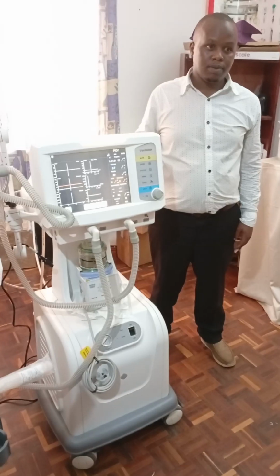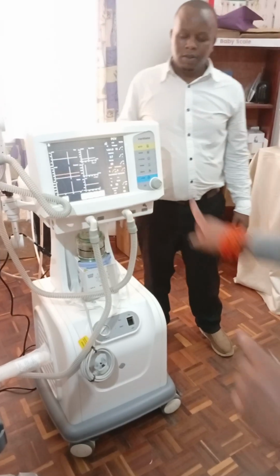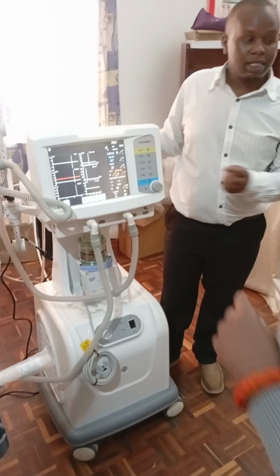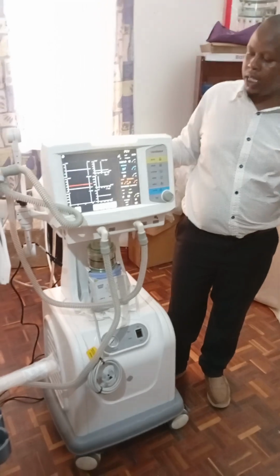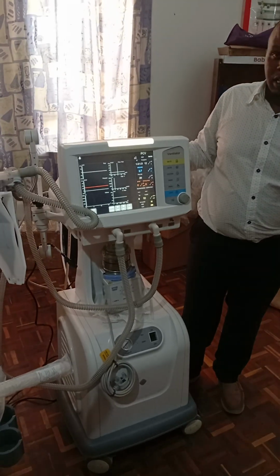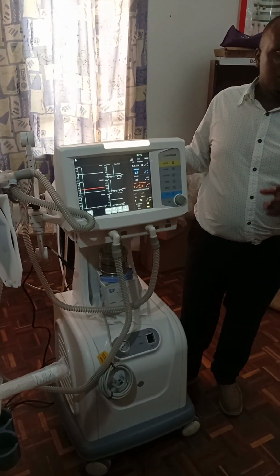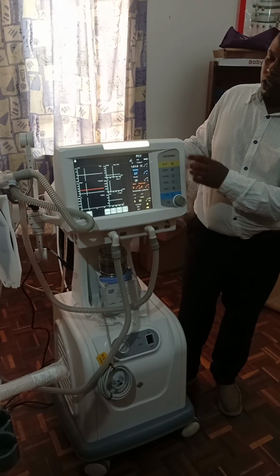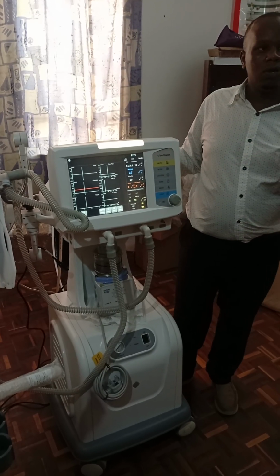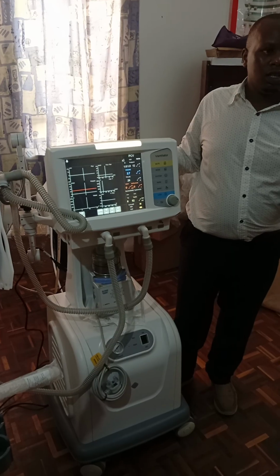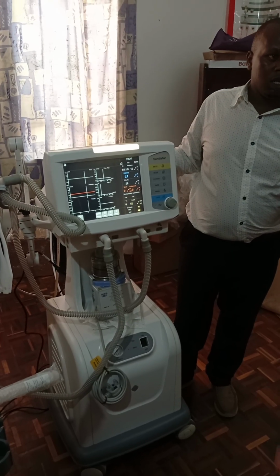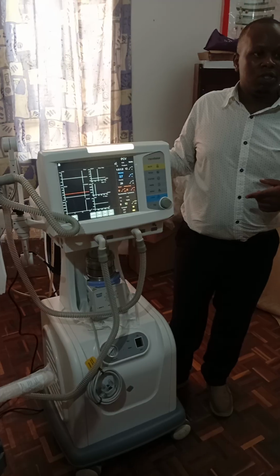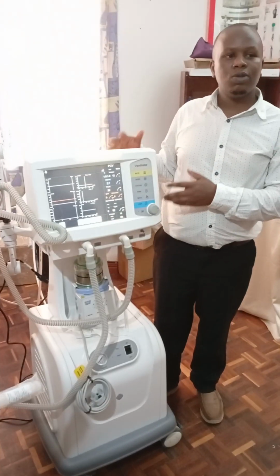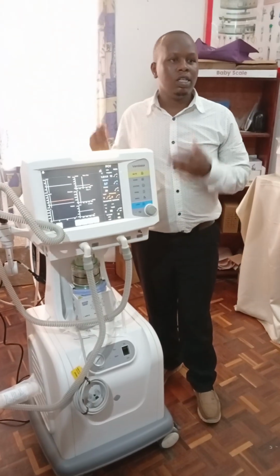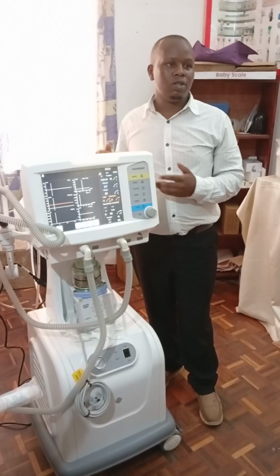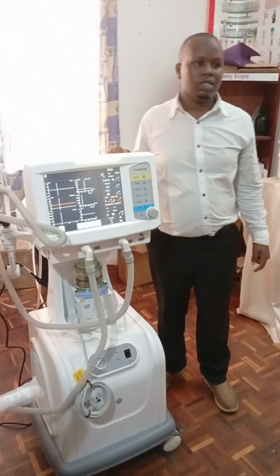So this button is for muting. If you press it, just like any other machine, like the anesthesia machine and the likes, the alarms are meant to alert you. Even if you mute, you can only mute for 120 seconds. After 120 seconds, the alarm will come on again. Because this machine is used in a sensitive area, you'll need those alarms to always be on for you to know what's happening to the patient.